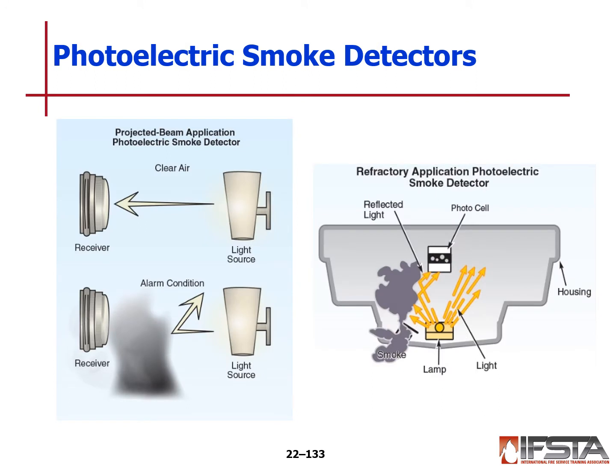This is kind of an explanation of how your photoelectric detectors work. When the products of combustion, and specifically the smoke, break that beam, because they have a light source inside there, that will trip the circuit to send the signal. In a refractory application of the photoelectric, you've got the lamp and the lights bouncing these beams. Again, when there's a disruption in those beams of light, that sends the signal from the photocell.